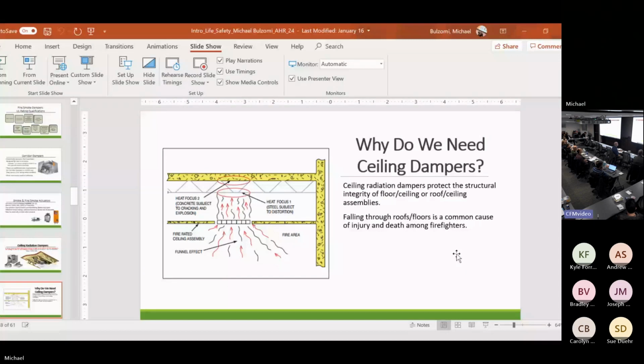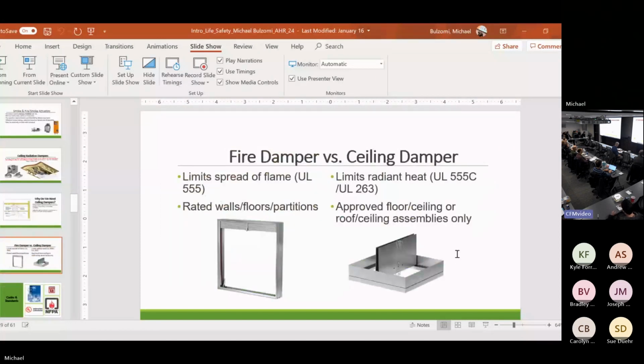If I don't protect that opening, I'm going to get this funnel effect. There's a fire in this room and a diffuser with a neck opening above it that was unprotected. The heat is going to find that hole. Everything else is rated. The heat will find that hole. It'll funnel, and it could affect the structural capabilities of the floor above it. If it's concrete, it can crack and explode. If it's steel, it can warp and bend or collapse. The leading killer of firefighters is injury from falling from buildings. We don't want that. So we protect those openings with ceiling radiation dampers.